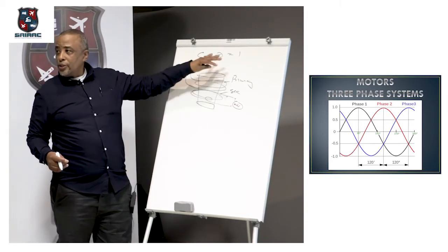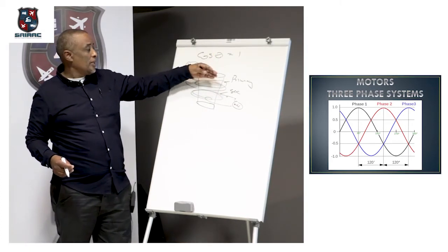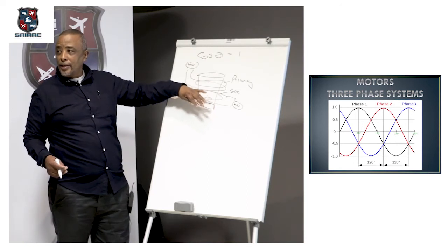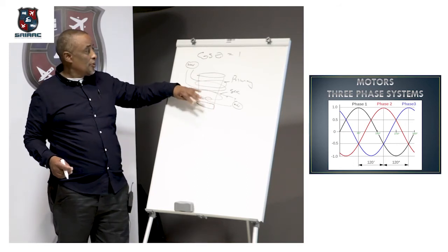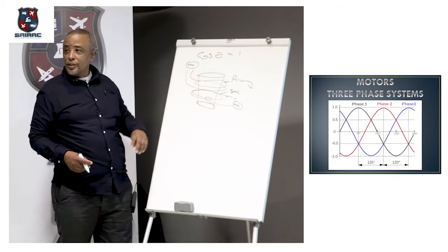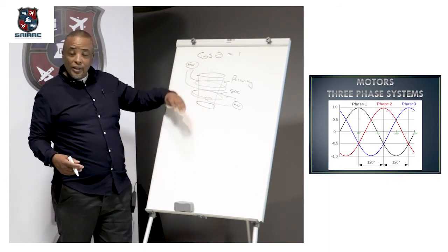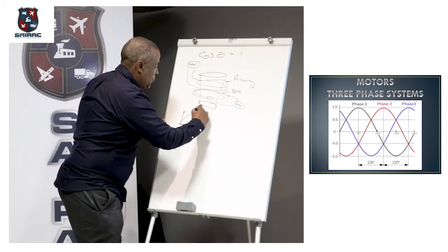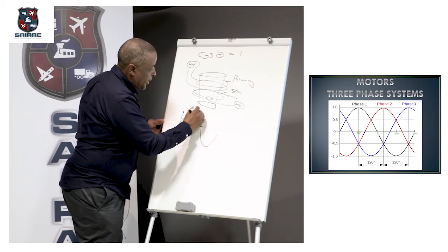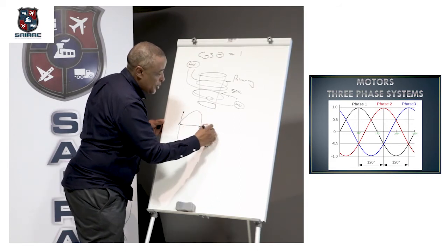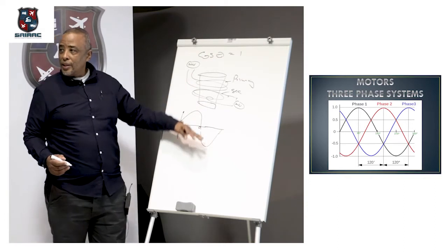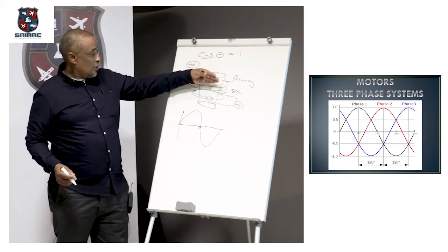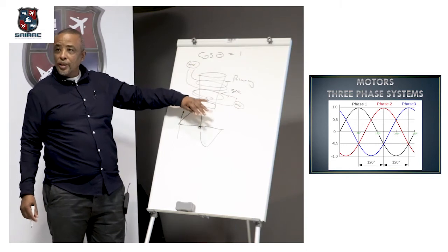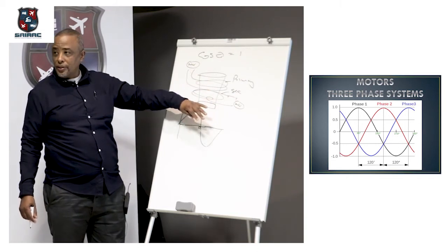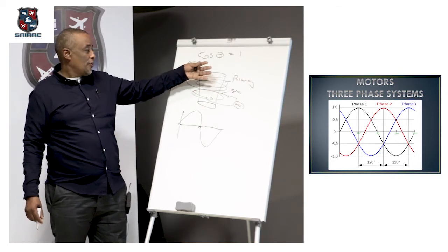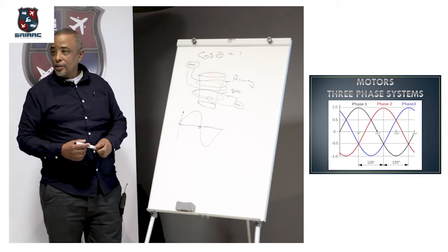Absolutely no electrical connection between the two. All the energy from the primary linking with the secondary is done entirely magnetically. Okay, that's what mutual induction says. If you place two coils next to each other on the same core, they're expanding and collapsing. It expands, collapses, expands, collapses. The expanding and collapsing magnetic field on the primary will link with the secondary, and the magnetic field will be introduced into the secondary. So the transfer of energy from primary to secondary is done entirely magnetically.